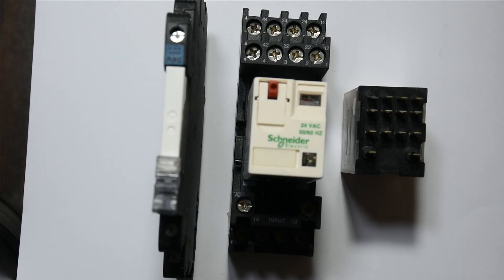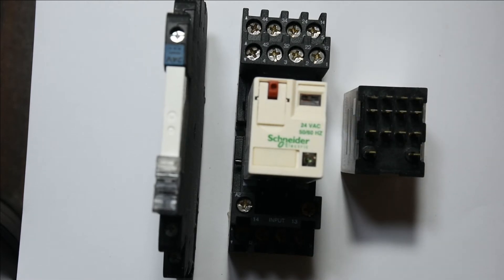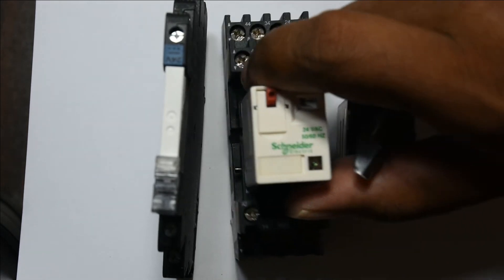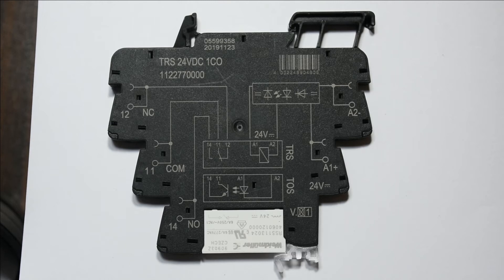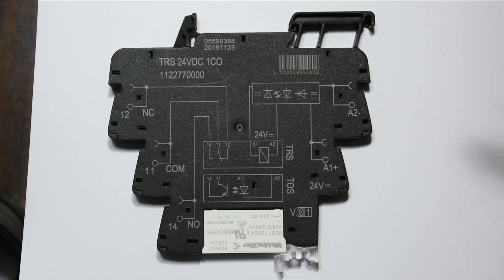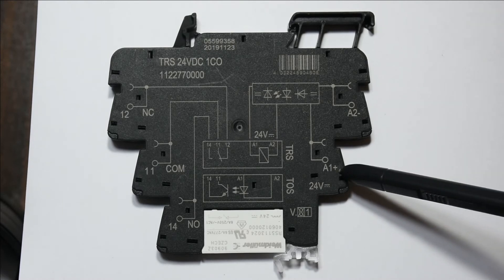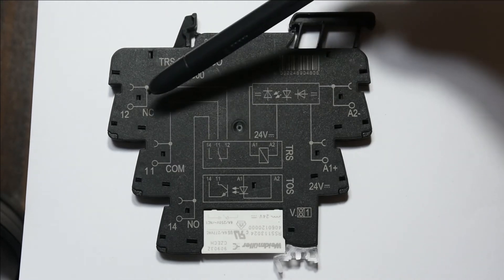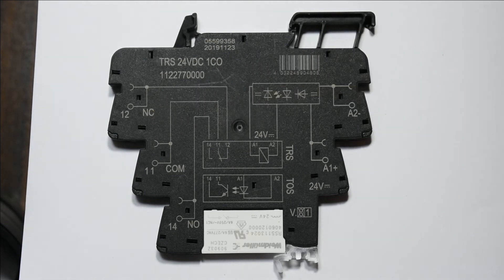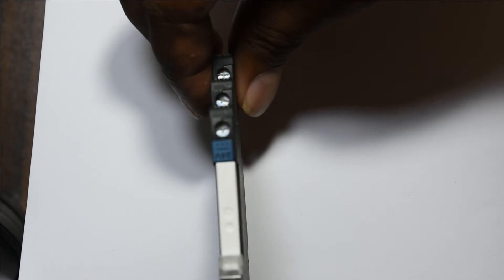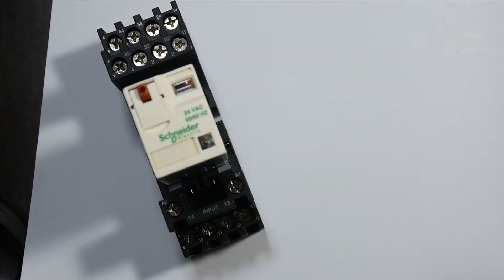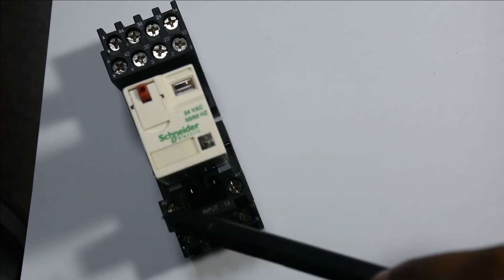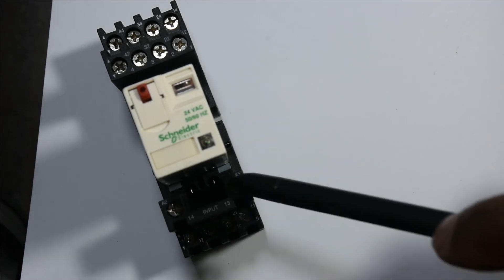Now I will explain the connection of this relay. From the PLC you will connect the ground to this terminal, and the 24 volt from the PLC goes to the A1 plus terminal. Here you have the common contact, and depending on your situation you can use the normally closed or normally open. This relay has A1 and A2, two terminals for the coil.